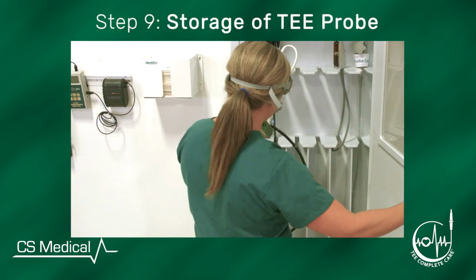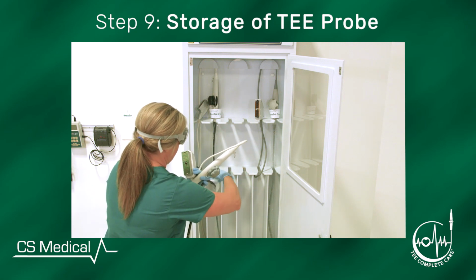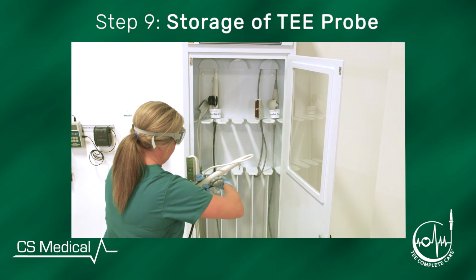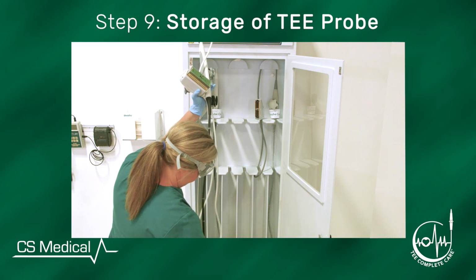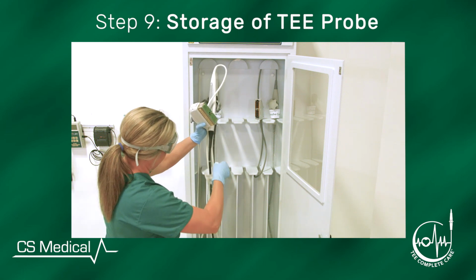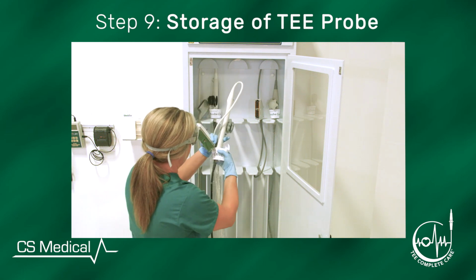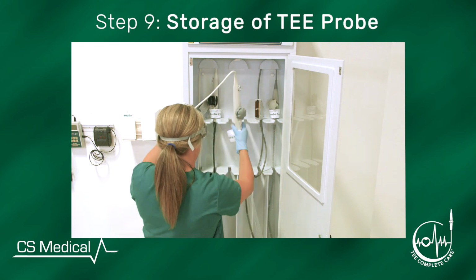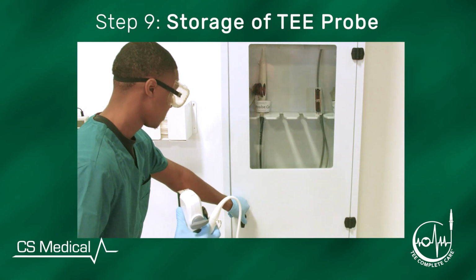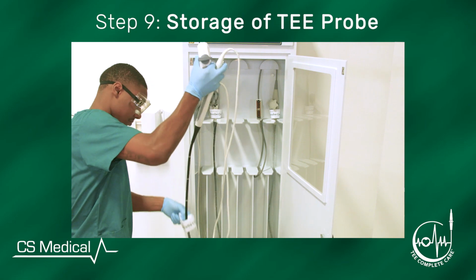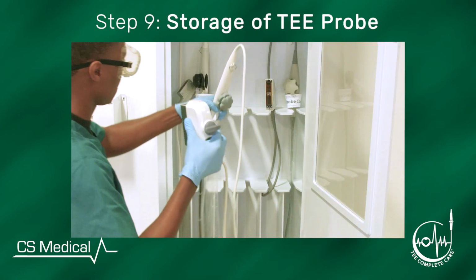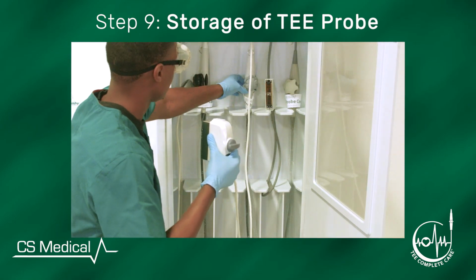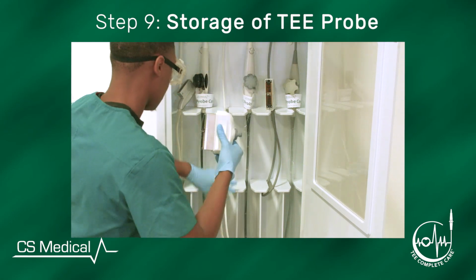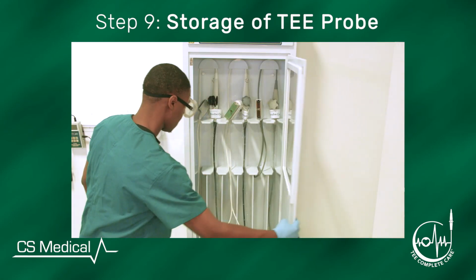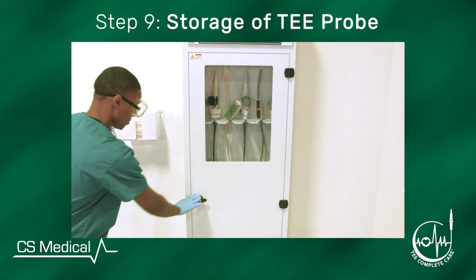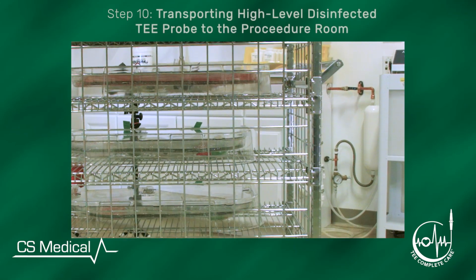Step 9. TEE ultrasound probe storage. TEE ultrasound probes should be stored in a dry environment, hung vertically, and within a HEPA-clean cabinet. The Clean Shield TEE ultrasound probe storage cabinet allows healthcare facility compliance with the Joint Commission standards of care. CS Medical provides the Clean Shield ultrasound probe storage cabinet, which bathes the high-level disinfected TEE probe with constant positive pressure HEPA filter airflow.